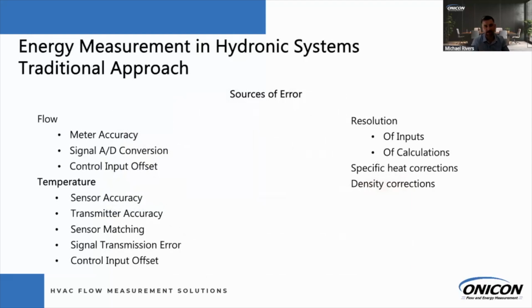So what ONICON did is that we identified all these different sources of error for that BTU calculation. And while this all comes into play, what we found is that most of the time, the inaccuracies were coming from the temperature sensors. And the reason for that is, RTDs, there's different qualities and grades out there, but easily could be a quarter degree off, a half a degree off, a full degree off. Well, even if it's a half a degree off on the supply and it's a half a degree off on the return, when you look at that delta T, that's potentially 1 degree off. So 1 degree off in a 10-degree chilled water system, you're looking at 10% error before you even start considering the other sources of error.